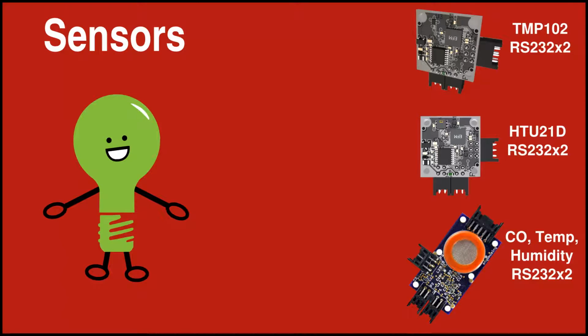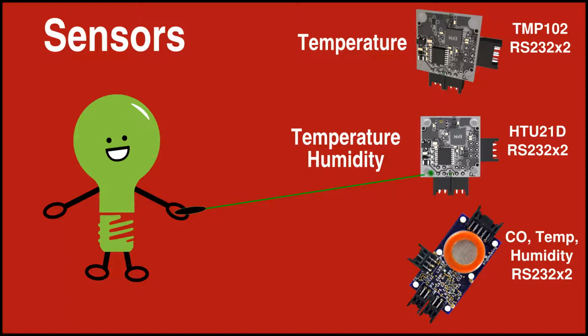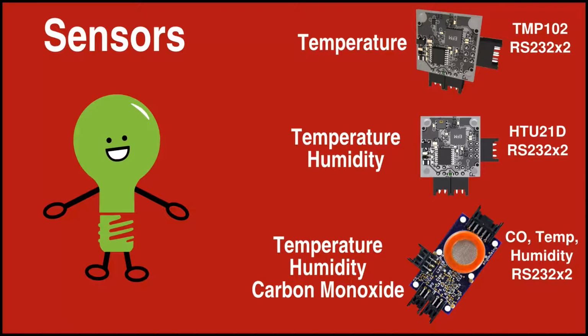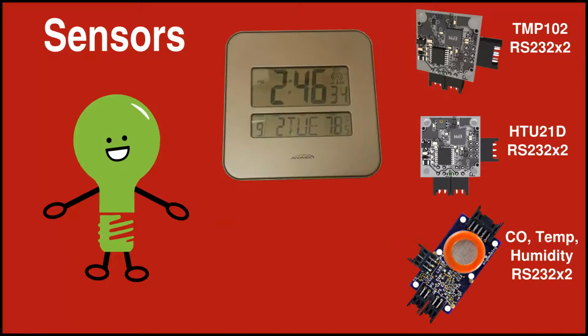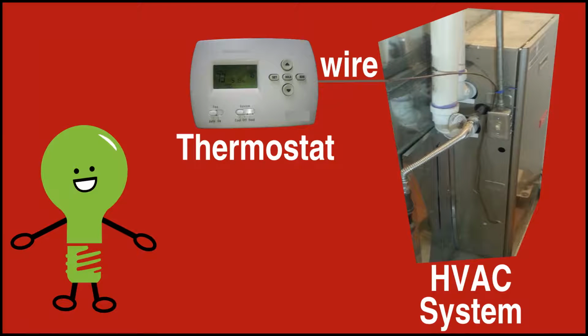A number of different types of sensors can be used in a system. The most basic system needs a temperature sensor, and it may be useful to have temperature sensors in more than one room. A sensor with both temperature and humidity is another option. If a heating system uses combustion, a carbon monoxide sensor can add a safety factor to the system. If the carbon monoxide level gets too high, the heating system can be turned off. Other inputs like the time of day are also useful to allow a schedule to be programmed into the controller. Now let's look at a real-world system.